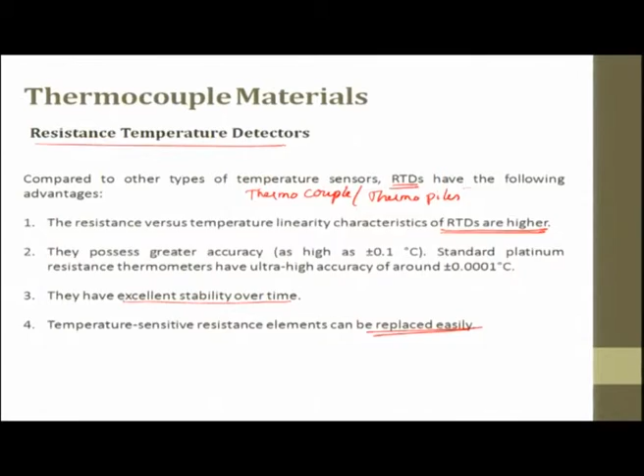This is how an RTD looks. A platinum lead is here. This is how it is exposed to the temperature, and then it is put inside a protective casing, and inside the protective casing the lead is wound around a ceramic bobbin. So, the temperature is measured, this is communicated inside, and there is a resistance element. These are resistance elements, the ceramic bobbin.